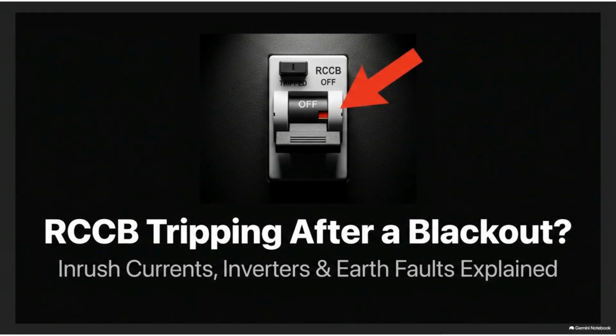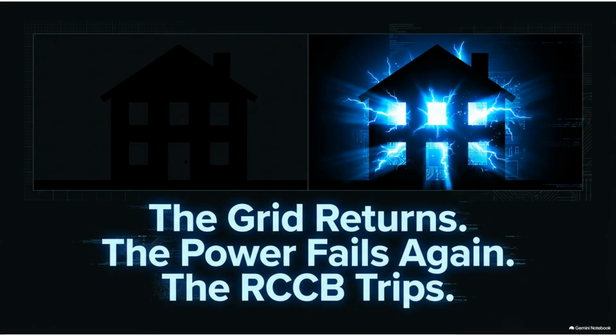Does your RCCB trip immediately after a power blackout? This video explores the reasons behind this, covering inrush currents, inverters, and potential earth faults. It is a frustrating scenario. The power grid returns after an outage, but then the power fails again because your RCCB has tripped.